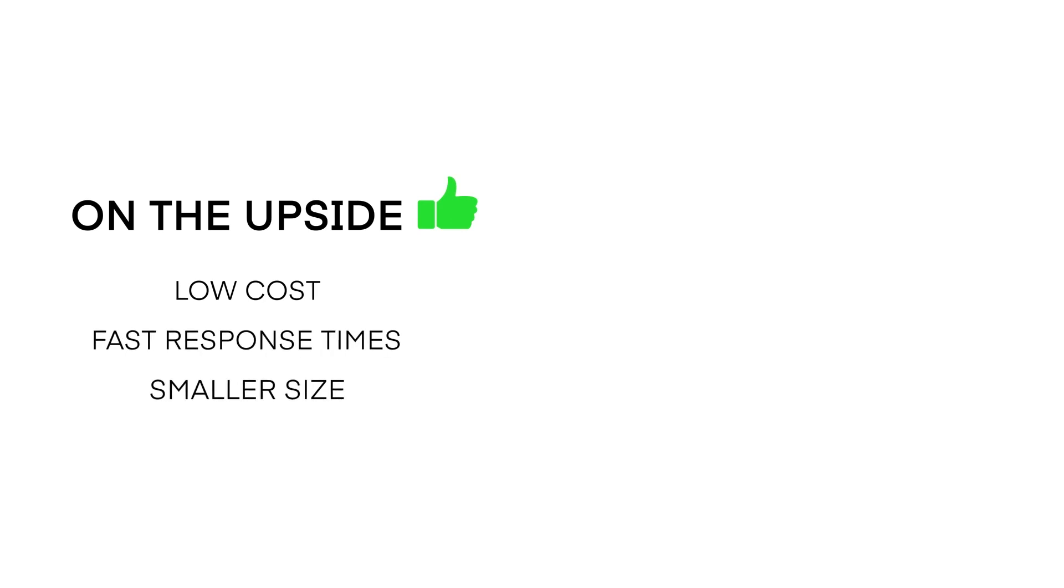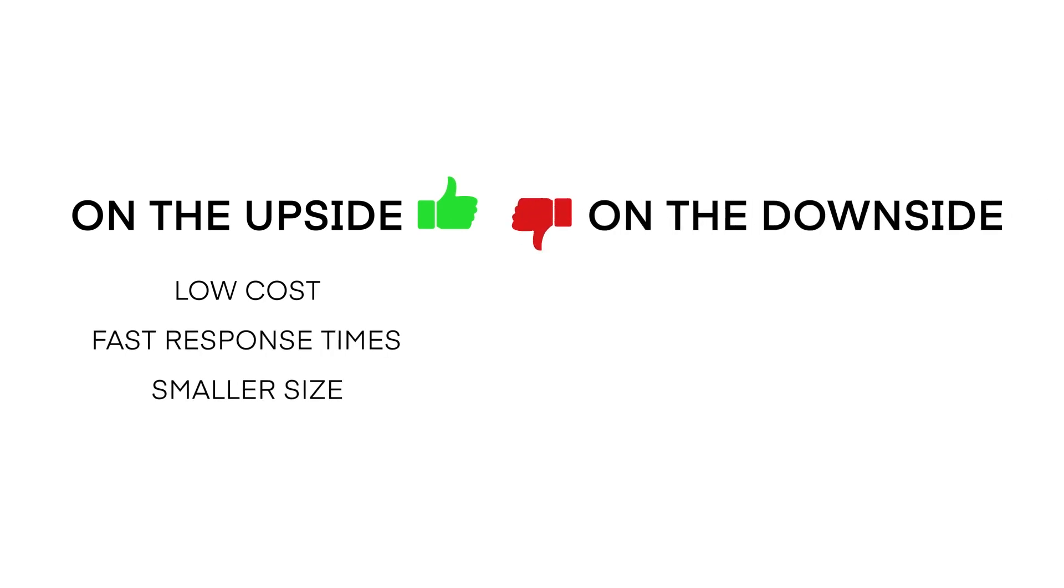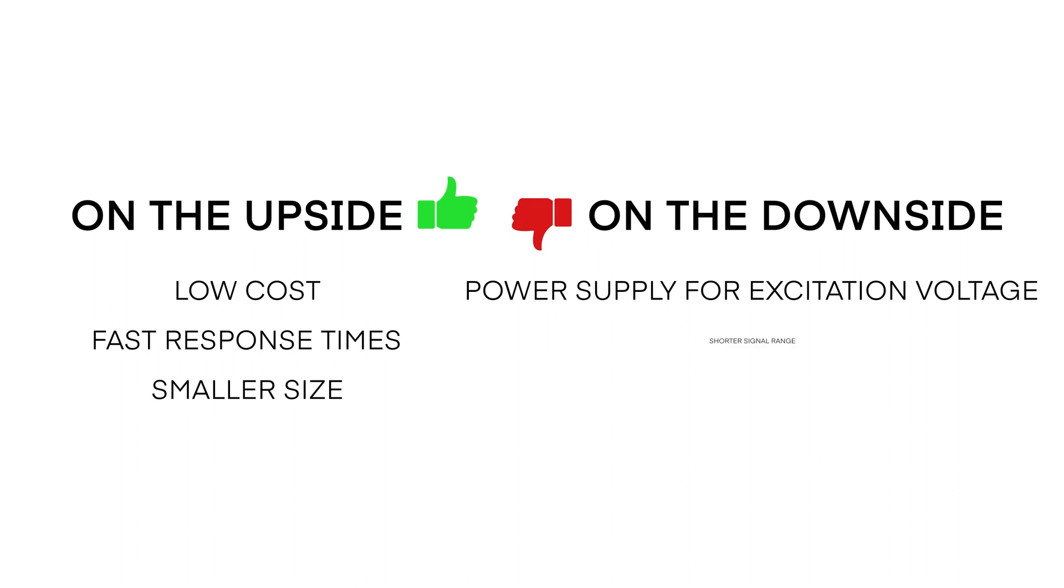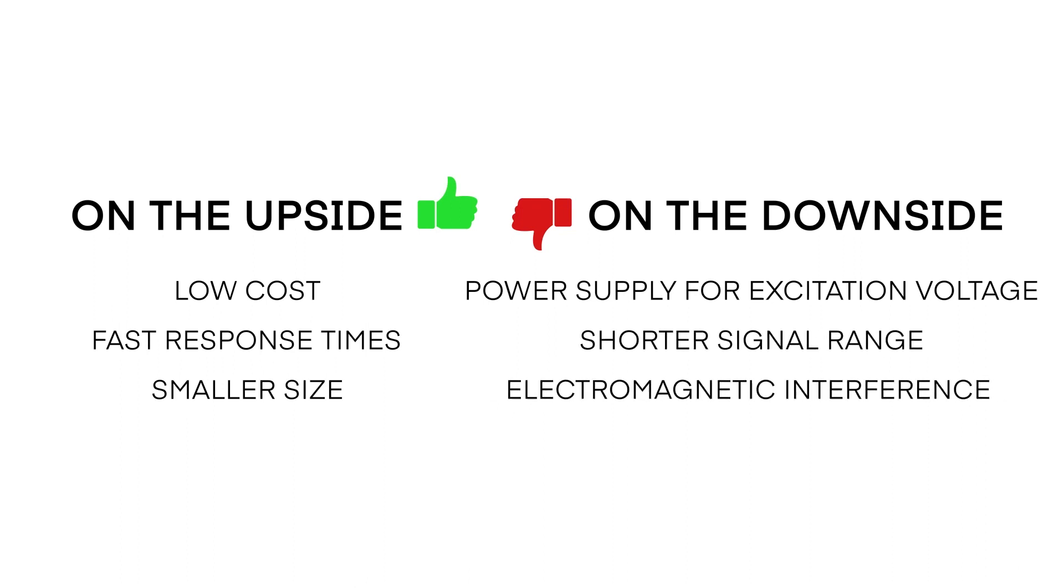The upside to millivolt per volt output is low cost, fast response times, and smaller size. The downside is the need for a regulated power supply to provide excitation voltage, shorter signal ranges, and they're vulnerable to electromagnetic interference.